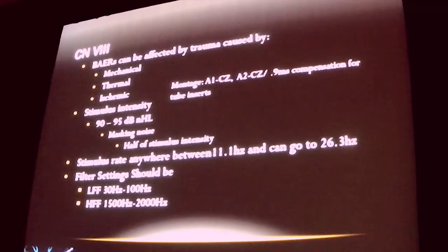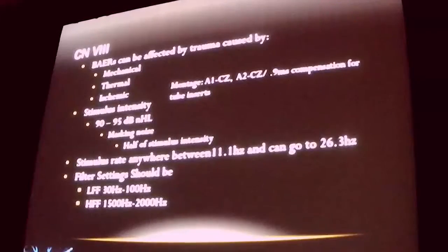Stimulus rate anywhere between 11.1 hertz and 26.3 hertz. You have to manipulate your settings accordingly to get the best BAER waveform. Here's a filter, low frequency filter 30 to 100, and a high frequency filter 1500 to 2000. Guys, why do we use a masking noise?